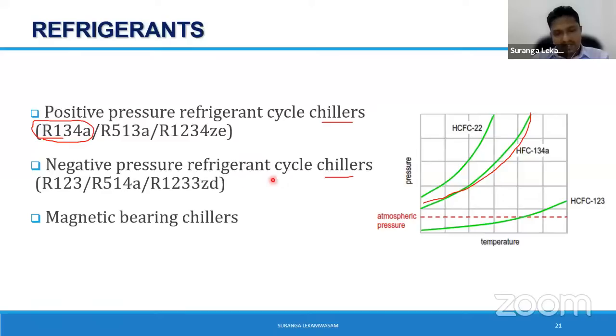But negative pressure refrigerant chillers are basically such that the condenser still operates at positive pressure, but your evaporator operates at negative pressure compared to the ambient. You can see your evaporator operates at negative pressure compared to the ambient. So what happens if there is a leak in your heat exchanger? Ambient air goes into the heat exchanger and makes big trouble, because air has a lot of moisture, which becomes liquid and sometimes ice. It goes and blocks, probably, your expansion devices, so there are issues. So if you go for negative pressure chillers, purging systems are essential, right? The common chillers in the industry in the centrifugal range use R123, right? So there has to be a sort of purging system for you to look at this issue.